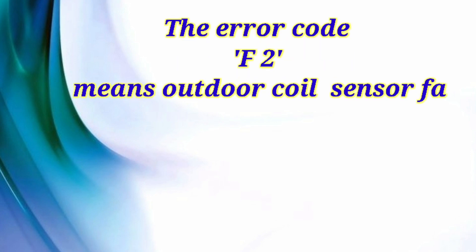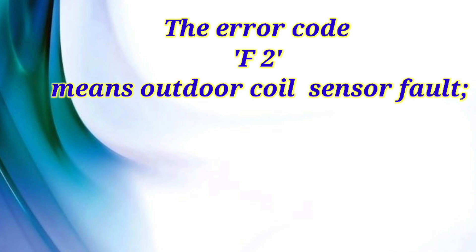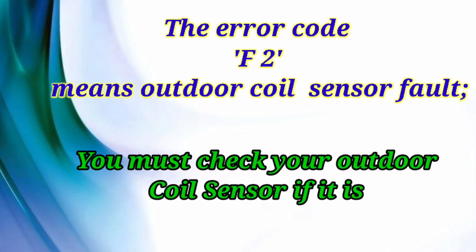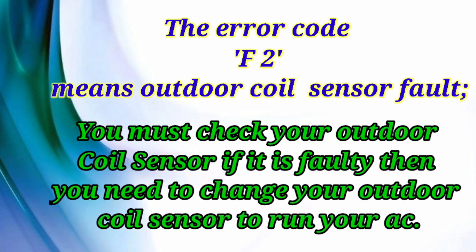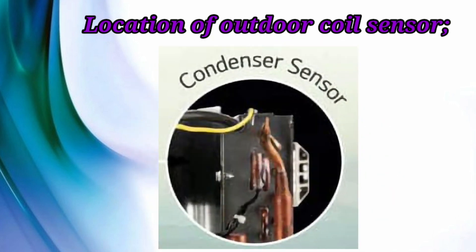Error code F2 means outdoor coil sensor fault. You must check your outdoor coil sensor — if it is faulty, you need to change it to run your AC, otherwise it will not work. This sensor is also called the condenser sensor, and you can see its location on the outdoor unit.